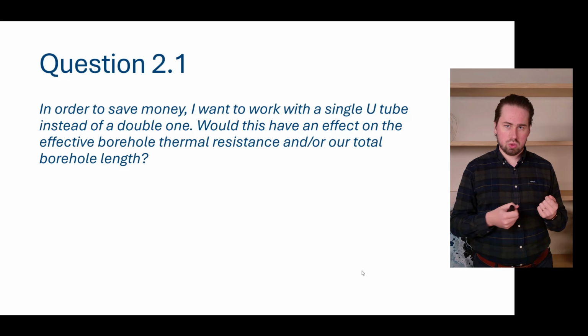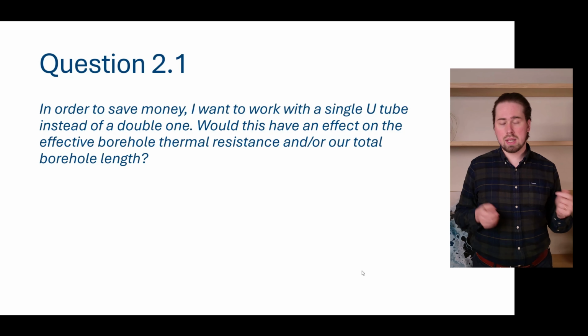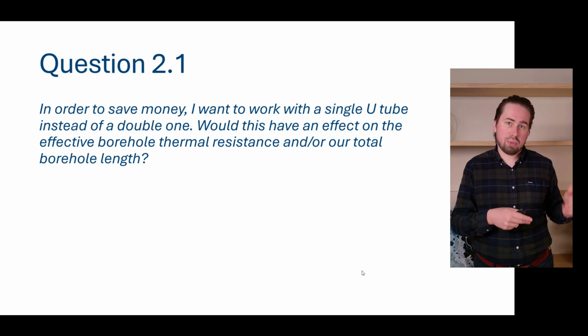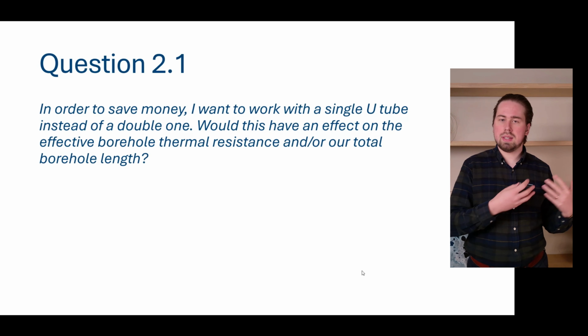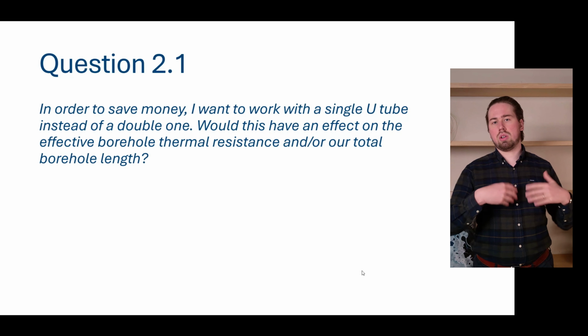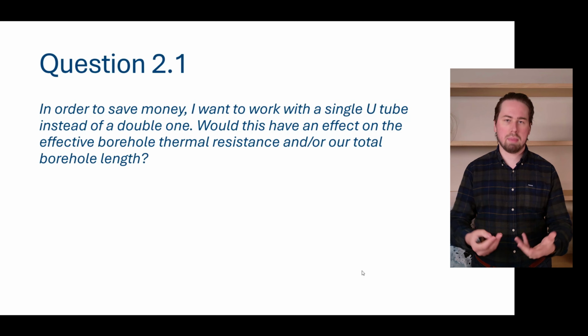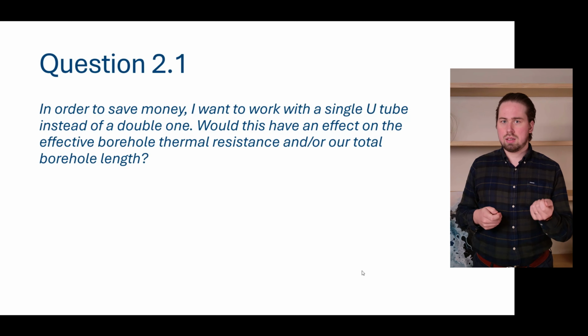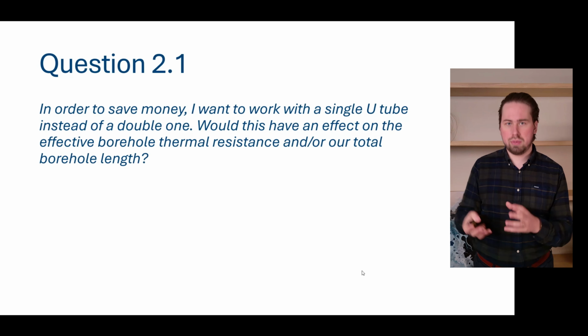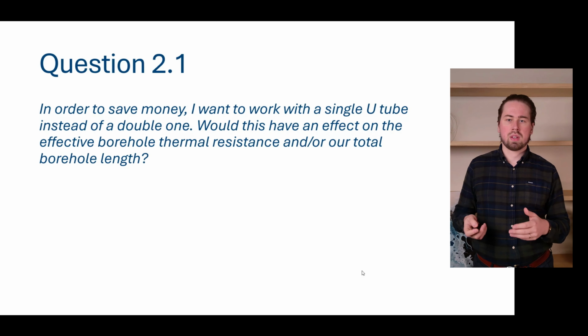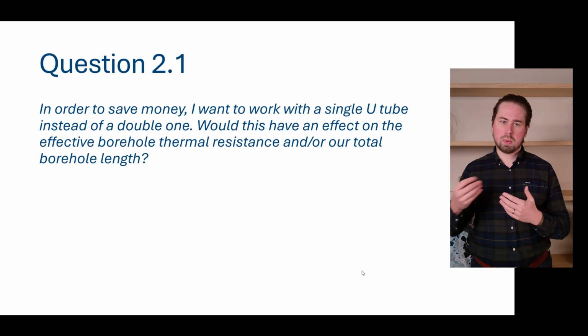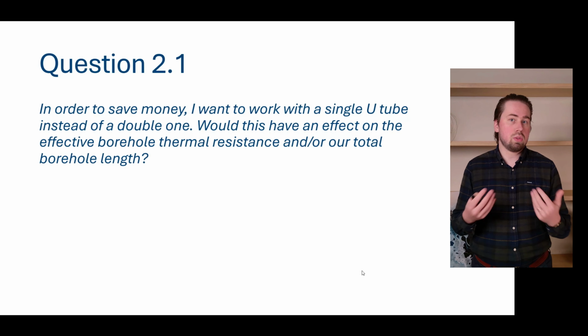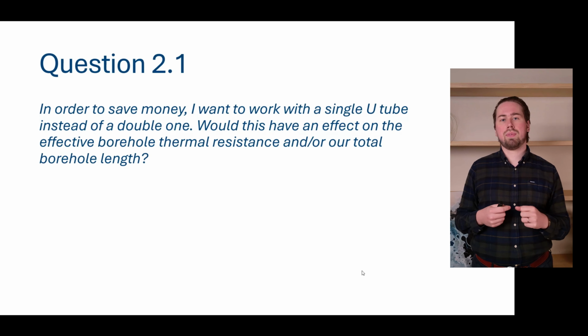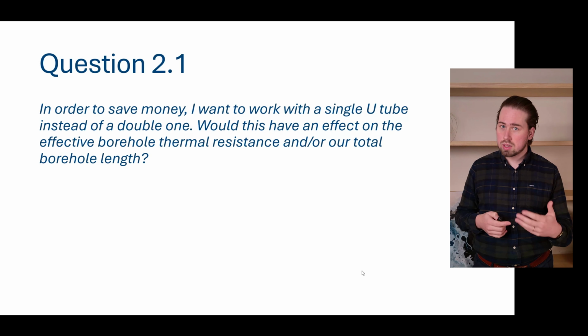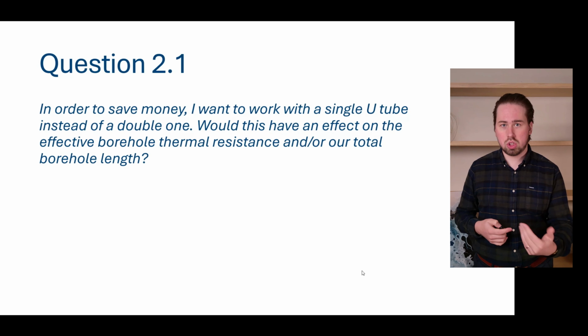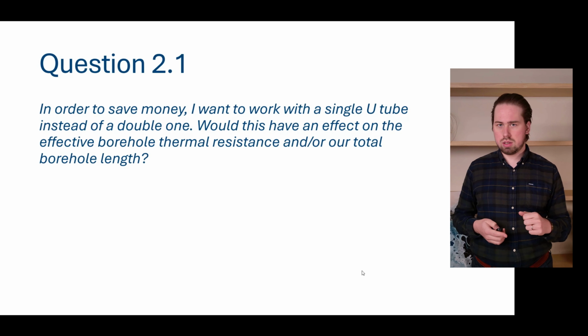If we move to a single U-tube, the fluid could become turbulent, because now twice the amount of fluid is passing through a U-tube. That means our convective heat transfer is way better, to the point that it compensates for the fact that we now have only half the surface area to transfer heat. So if you go from a laminar to a turbulent flow when switching from a double to a single U-probe, the single U-probe could have a better borehole thermal resistance and hence also a slightly lower total borehole length. So it's actually also cheaper looking at the installation or drilling costs.